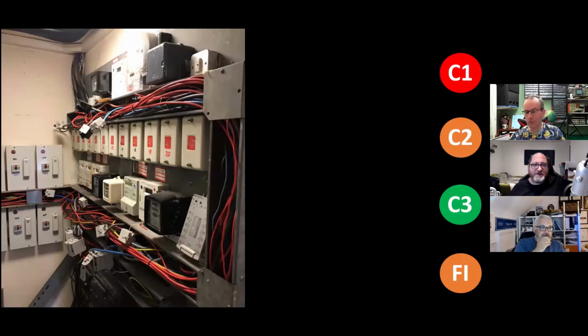There's definitely key meters there. They've gone in and changed the check meters for key meters. Those square white ones on the far left there, and the one in the picture, those are definitely key meters. There's 5 in there, I think. Can I give that a C1, please? Yes. I was on C2 until someone pointed out the key meters. I was like, oh, shit. That's a good point. Key meters, man. The burden... Yeah.